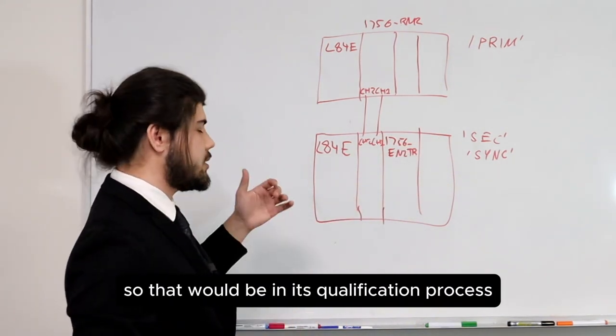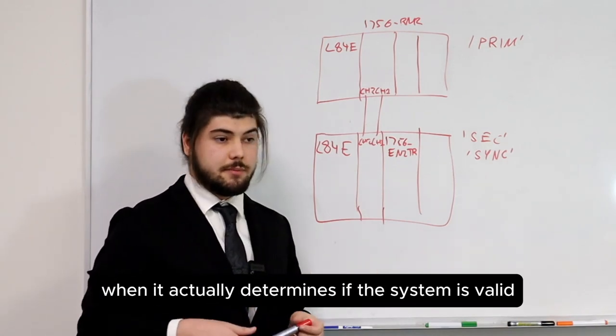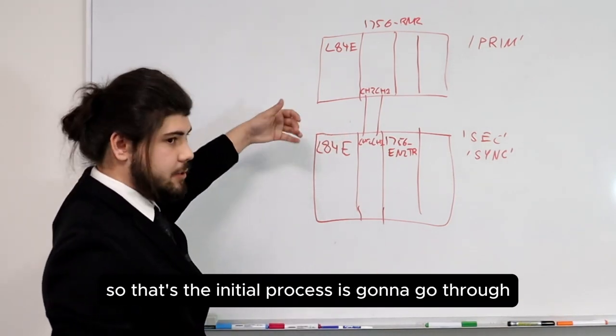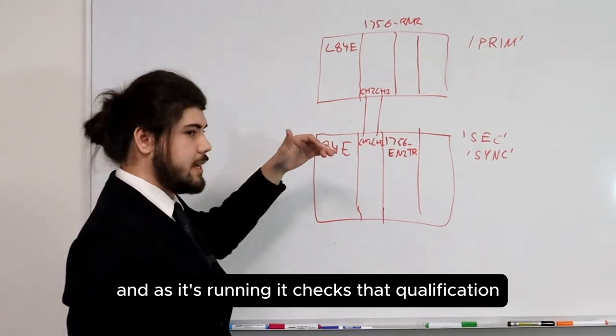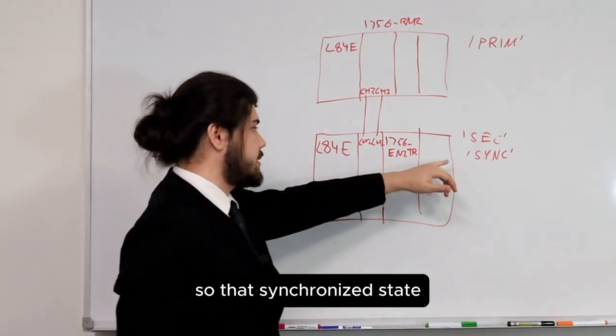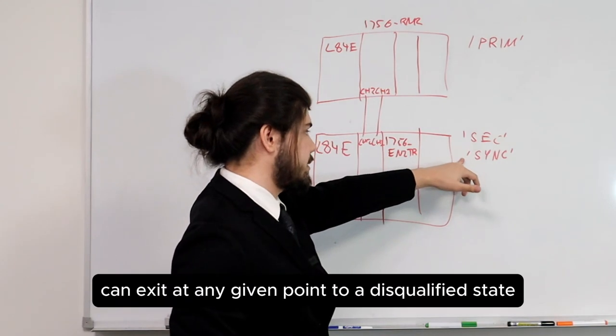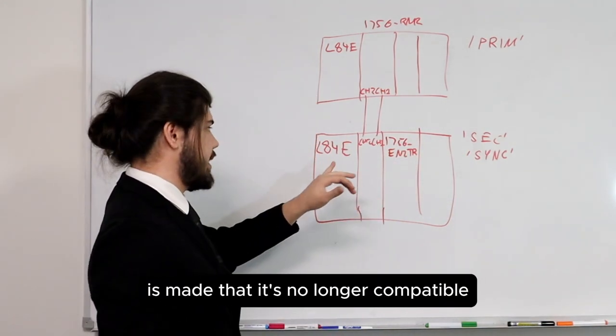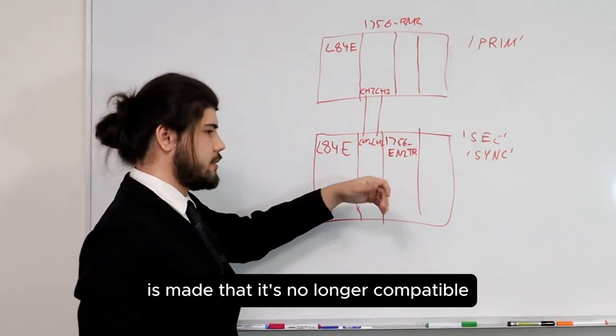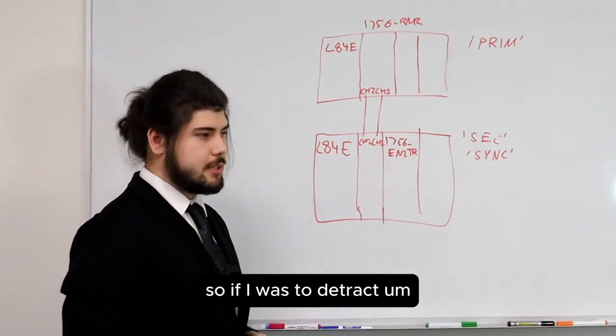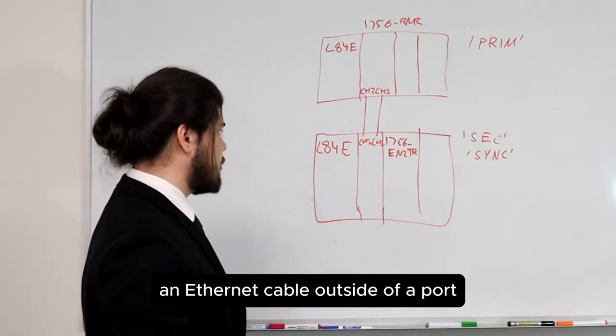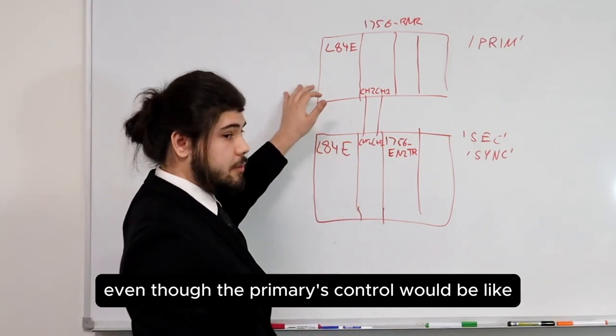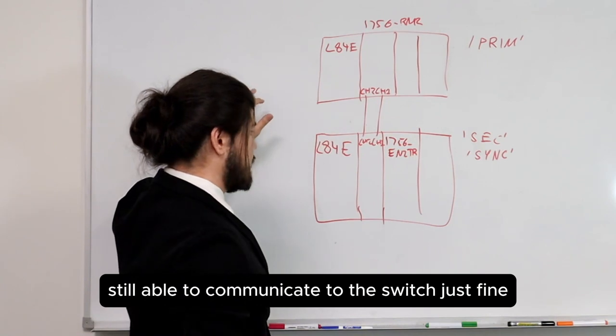When the system takes over it's expecting all of the hardware to be identical, and if nothing is plugged in it can't simulate and replicate nothing. That is part of its qualification process — when it determines if the system is valid to form a synchronized pair. As it's running, it continuously checks that qualification. The synchronized state can exit at any given point to a disqualified state as soon as it detects it's no longer compatible. For example, if I were to detach an Ethernet cable from a port, it would lose its ability to replicate that system, even though the primary control would still be able to communicate to the switch just fine.